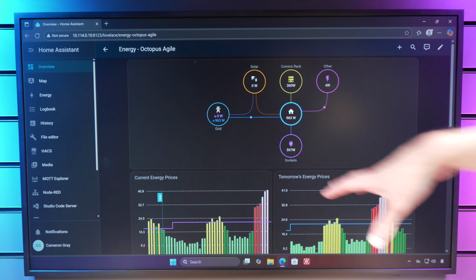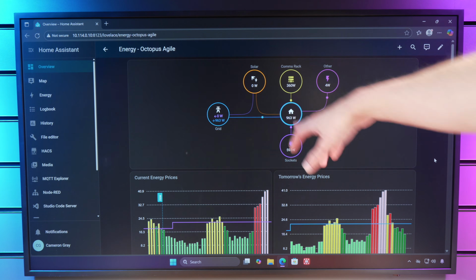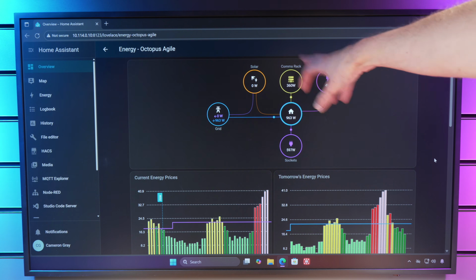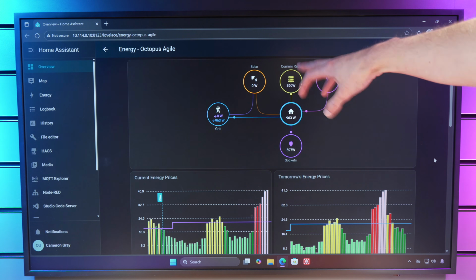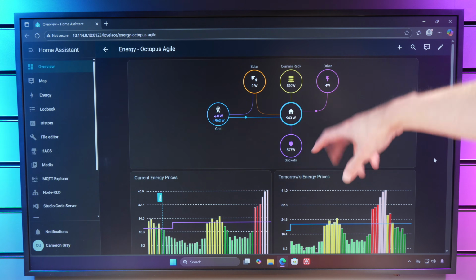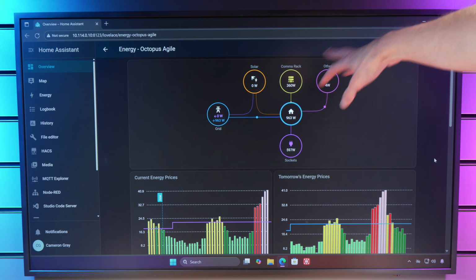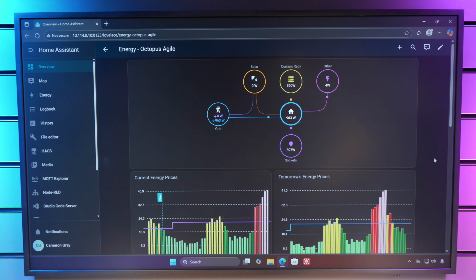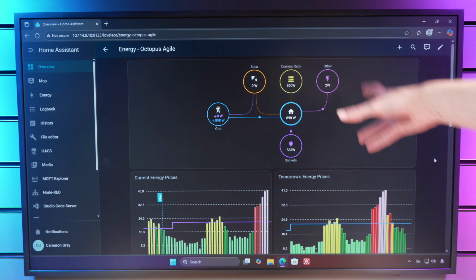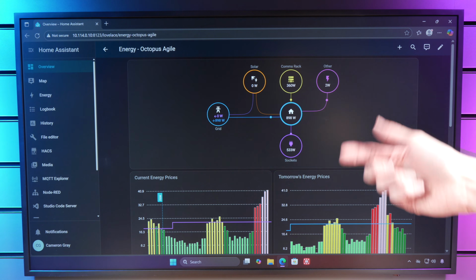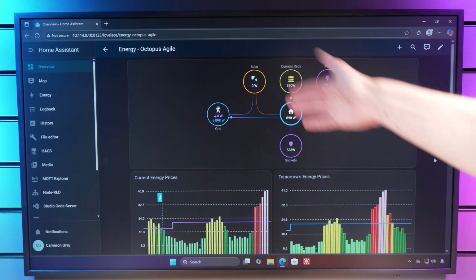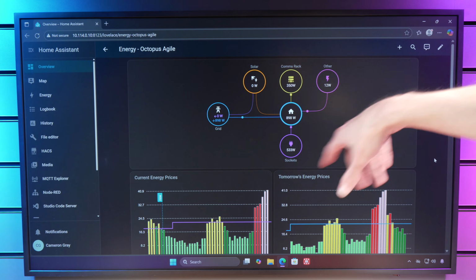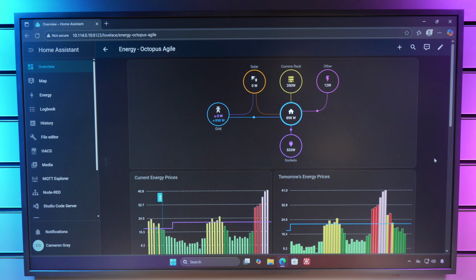And then finally back here, we have this live power dashboard. We can see power coming in from the grid, going out to the comms rack. That power is now coming from the PDU's direct measurement rather than a CT. Sockets are all being monitored there. We've got this other entity here that's going to be everything else, so kitchen, lighting, smoke alarms, boiler, that kind of stuff. These numbers probably still won't exactly add up. There's always going to be little bits of errors in there. And also you need to factor in these will all be sampled at completely different times to each other, so they might not completely line up, but it's a lot more accurate.